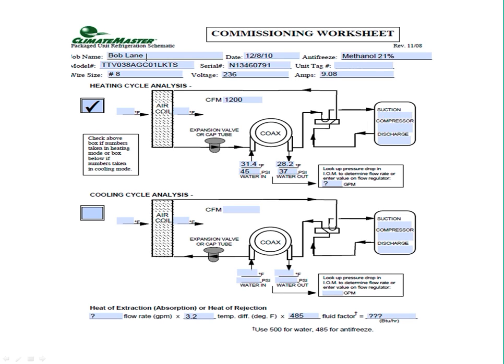Well, what are we going to do here? Well, this could be one of those. I've seen many out there because of installers that install by rule of thumb. They may have put 2 flow controllers or 2-pump flow controller on this particular 3-ton unit. So I would recommend you power the system down, disconnect the power to one of those 2 pumps, again, after you powered it down so you can do it safely. Power the unit back up and see if that is what all you needed to do.